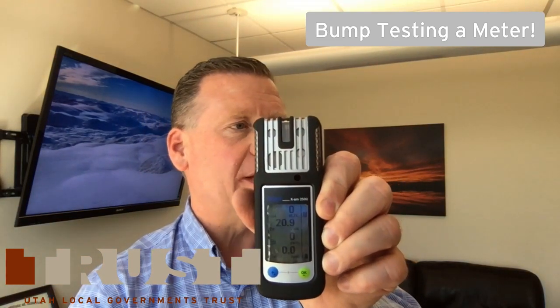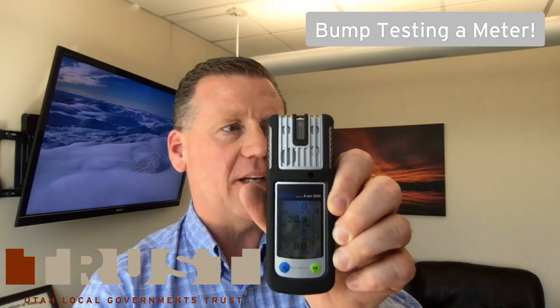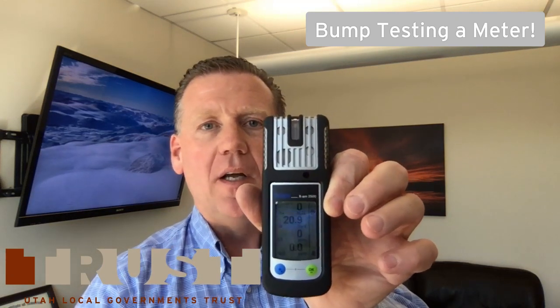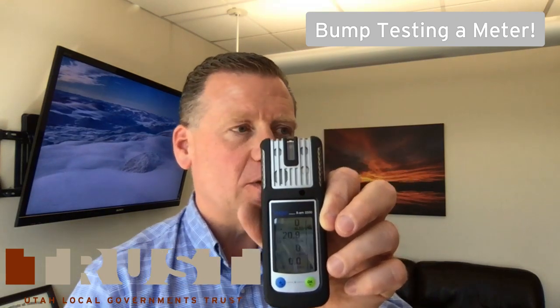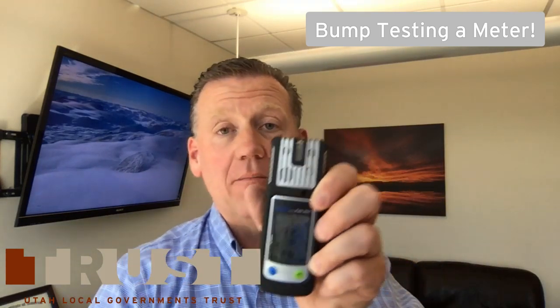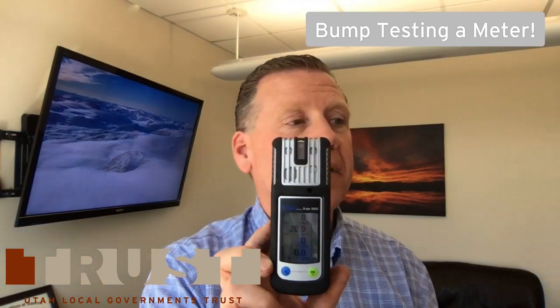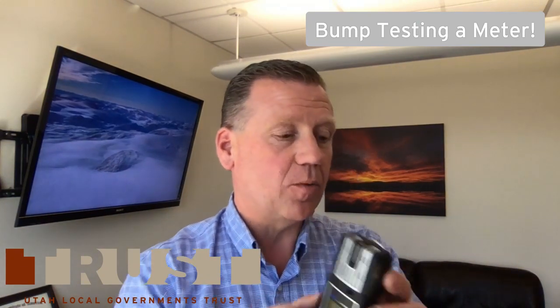We're sitting at 0, and a little bit of fluctuation there is okay. So if I'm hitting a -1 on carbon monoxide, I'm not going to get terribly worked up over that. However, if I'm out 4 or 5 parts per million, something like that, I definitely want to make sure that that's calibrated appropriately. Okay, so let's go through this.